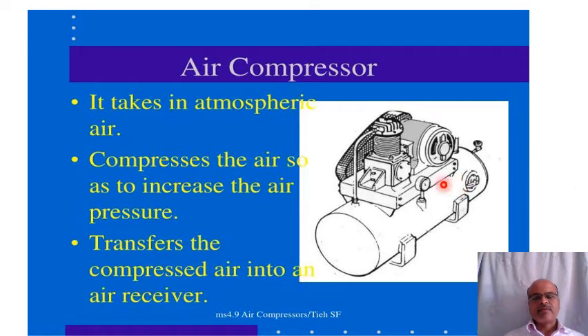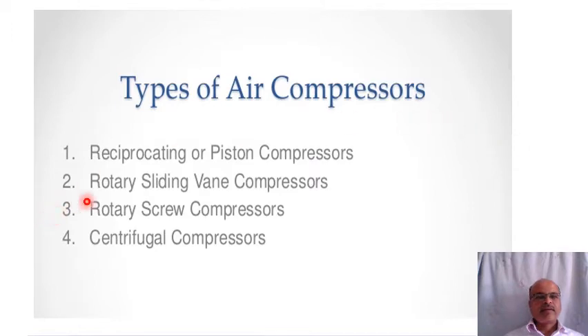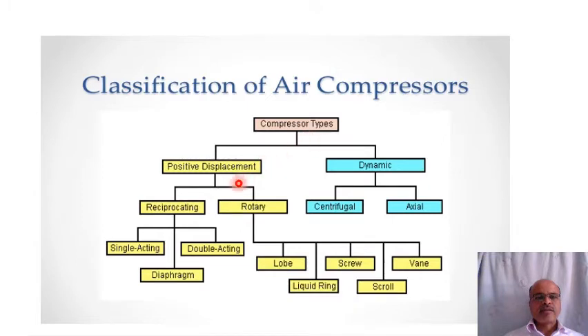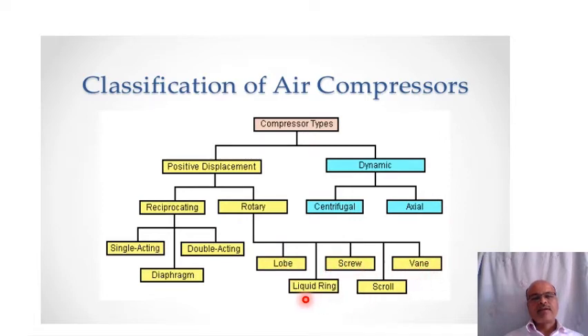This diagram shows different types of air compressors: reciprocating or piston compressors, rotary sliding vane compressors, rotary screw, and centrifugal. The compressor types are classified as positive displacement or dynamic. Positive displacement is divided into reciprocating and rotary. Rotary types include lobe, screw, vane, liquid ring, and scroll compressors. Dynamic compressors include centrifugal and axial compressors.